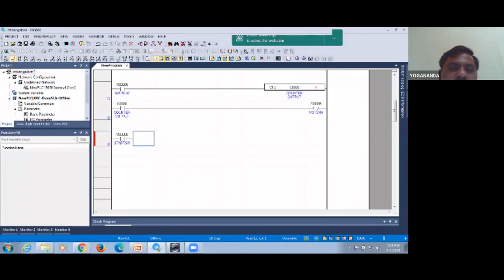Now next, this is the start switch, variable name. And one more input you need to check is the liquid level in the tank. If the liquid level in the tank is below the reference value, then only that switch is going to close. Otherwise, the switch is going to open. So that means below the reference, above the reference. If above, the switch indication is high; if below the reference, the switch indication is low. Because of this reason, I'm going to use a normally closed contact switch.